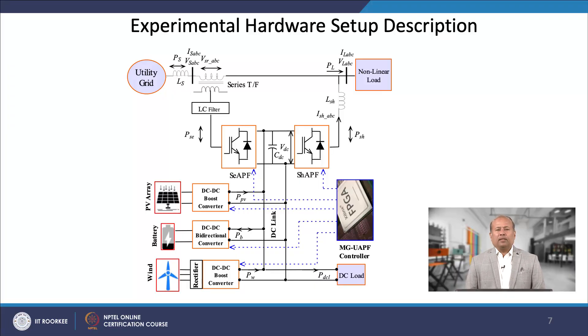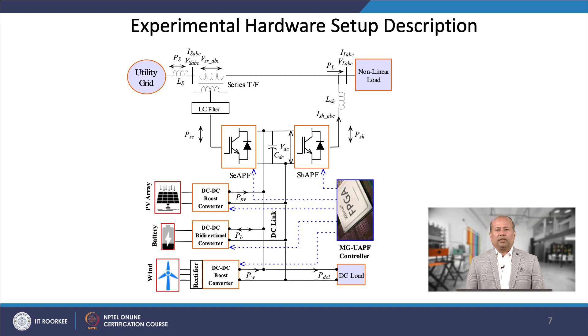Moving to the experimental hardware setup, here we can see the single line schematic diagram of the corresponding experimental hardware setup. It consists of two back-to-back voltage source converters (VSCs) connected through a common DC link between the utility grid and the load. The grid side converter acts as a series active filter connected through a series injection transformer, and the load side converter acts as a shunt active filter connected through an inductor. The series active filter behaves as a pure sinusoidal current source and offers a high impedance path for load harmonics. An LC filter is used to eliminate the switching harmonics.